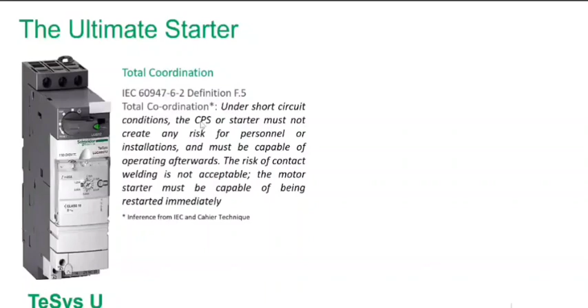If I want to understand this product in a better way, this is a combination of your protection device, which is your MCCB. It is a combination of your contactor, which is your switching mechanism device, and it is also a combination of your overload protection, which is thermal overload relay. So all three combined into one, we have developed this unique starter. So this starter is available for up to 15 kilowatt of DOL and RDOL applications only. So if you have your motor ratings up to 15 kilowatt for DOL and RDOL, this particular product can be used.